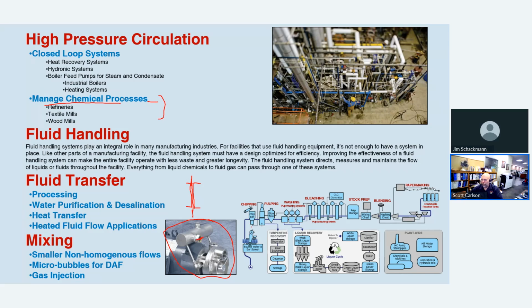And what the maintenance plan can do is, as the process is going, the maintenance person can walk by and shine a flashlight in there, or just look and see in there. And if the oil level is higher or lower or cloudy, then they know that the seal is leaking and it's time to change the seal. Oftentimes, the oil won't hurt the process as much as having a catastrophic failure of the pump, causing the entire system to bind up. So we have customers that are really happy that have that situation, that we have this available.